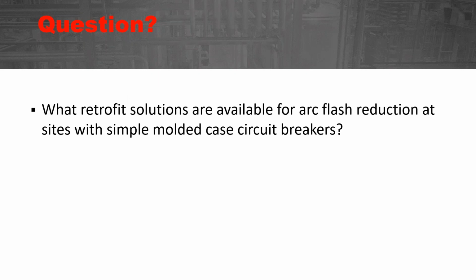Next question is for you again. What retrofit solutions are available for arc flash reduction at sites with simple molded case circuit breakers? I kind of just answered that question regarding the over-dutied equipment. Some retrofit solutions: there's equipment that can be installed on top of an MCC. There are ways you can modify an MCC where you do some additional bus work just next door or adjacent to it, then put a device in there and reconnect up to the MCC. Those could be a different breaker, could be a fuse, could be a current limiting device.